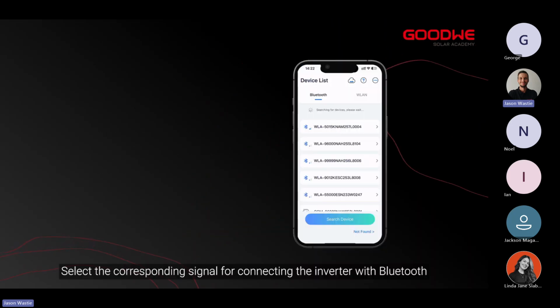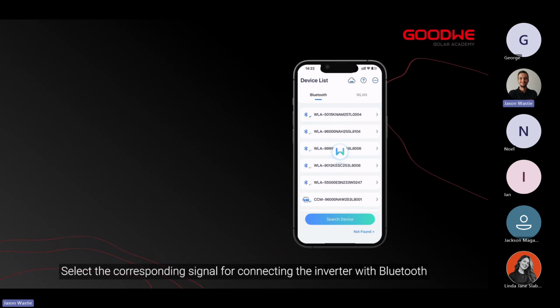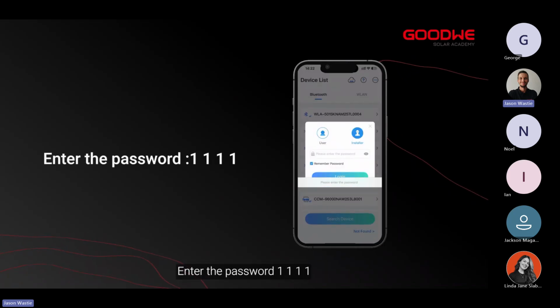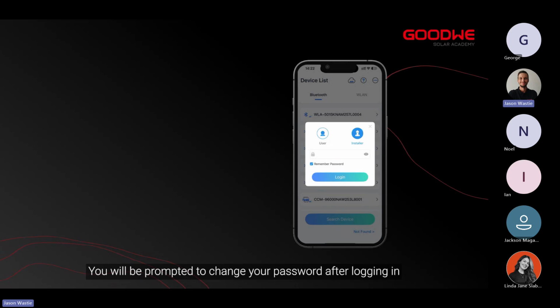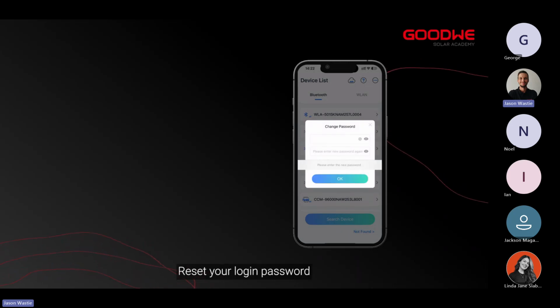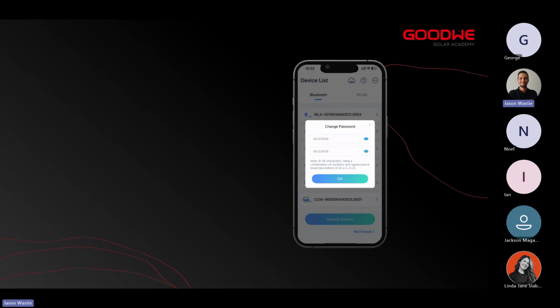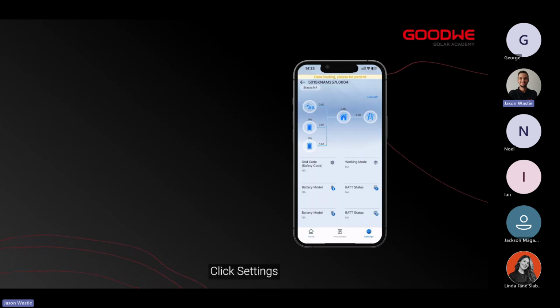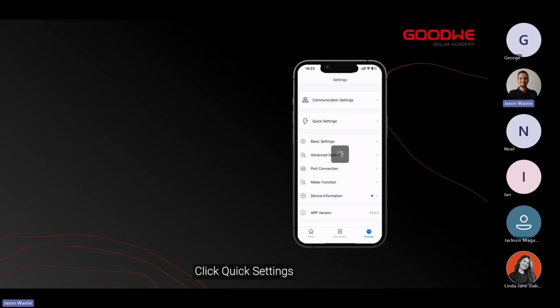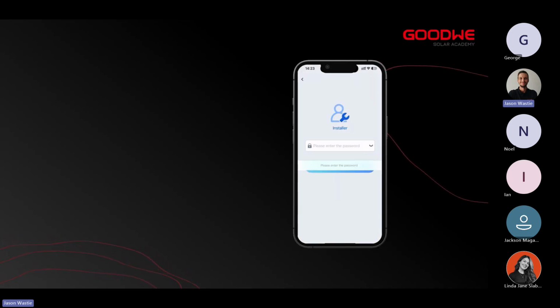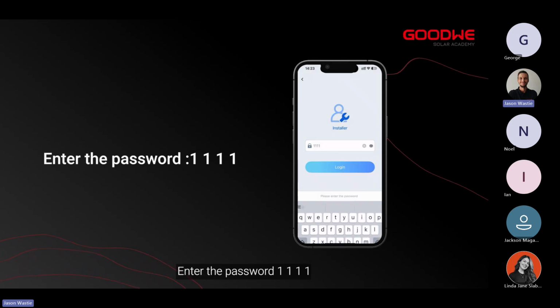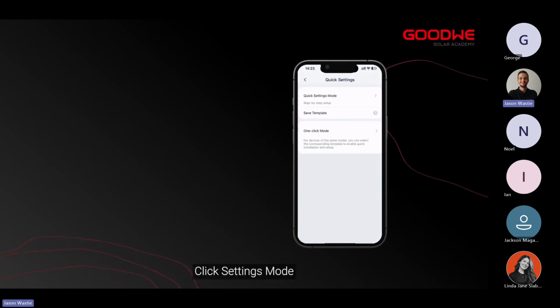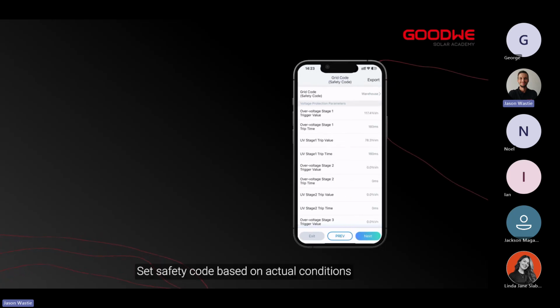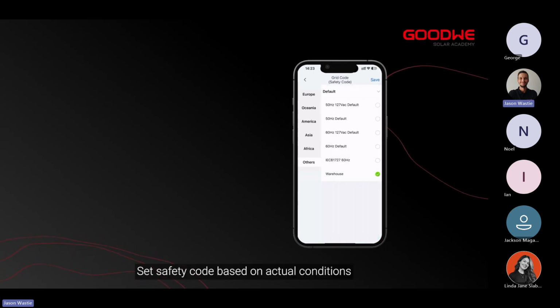First open the app. Select the corresponding signal for connecting the inverter with Bluetooth. Enter the password 1111. You will be prompted to change your password after logging in. Reset your login password. Click Settings. Click Quick Settings. Enter the password 1111. Click Settings Mode. Set safety code based on actual conditions.